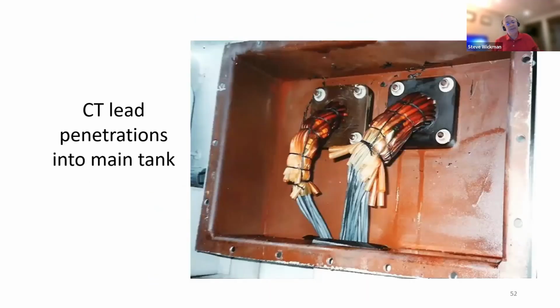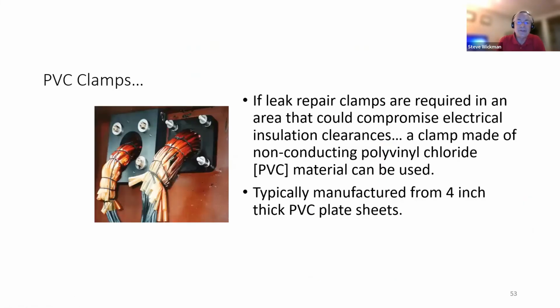CT lead penetration is going into the main tank. Here's the hockey pucks, as they're referred to sometimes. The gasketing on those has a propensity to fail, and you can see the oil running down from the one on the right there. In this situation, we will fabricate a clamp made out of a PVC material, hollowed out on the inside, to put the sealant up around that component and contain that leak.